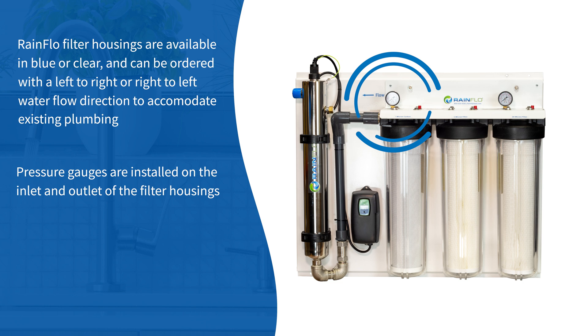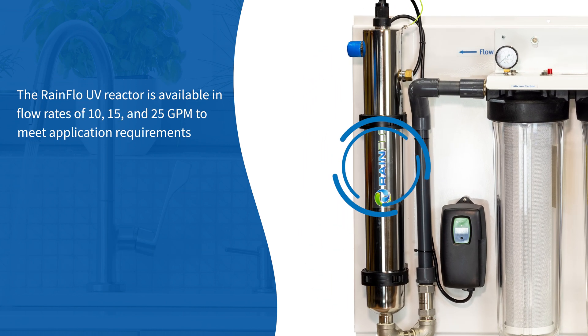Pressure gauges are installed on the inlet and outlet of the filter housings. A 7 psi difference indicates it is time to replace the filters. The RainFlo UV reactor is available in flow rates of 10, 15, and 25 GPM to meet application requirements.